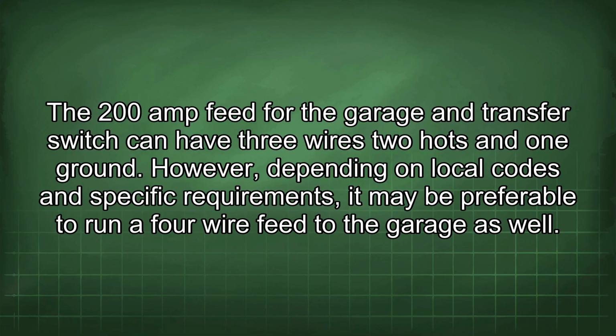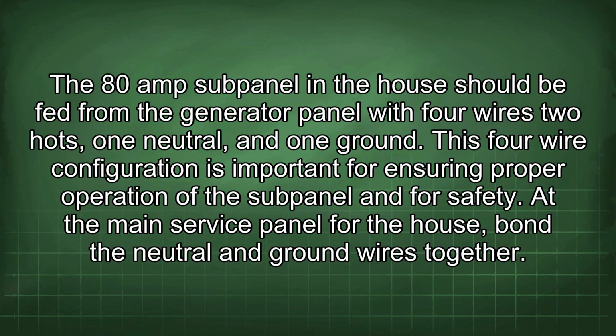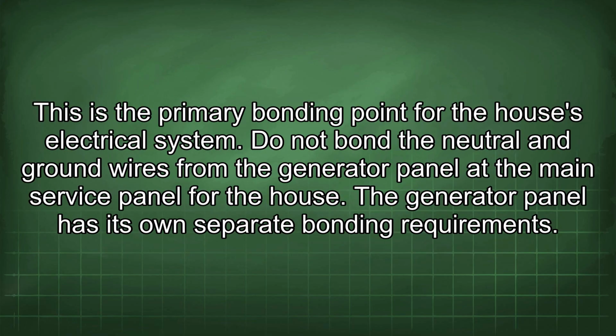as well. The 80 amp subpanel in the house should be fed from the generator panel with 4 wires: 2 hots, 1 neutral, and 1 ground. This 4-wire configuration is important for ensuring proper operation of the subpanel and for safety. At the main service panel for the house, bond the neutral and ground wires together. This is the primary bonding point for the house's electrical system.